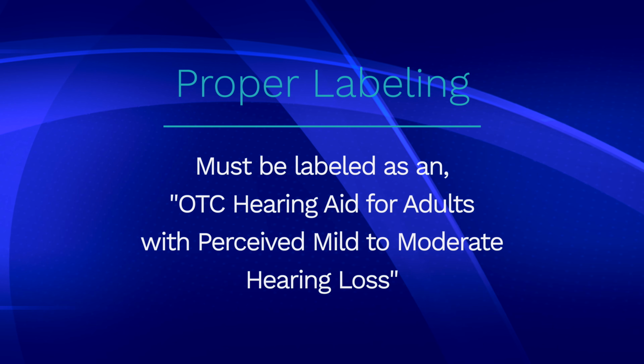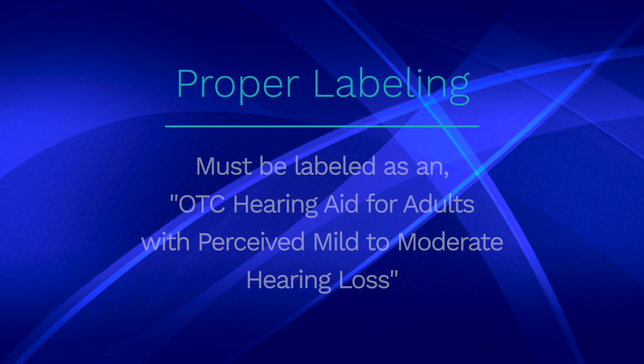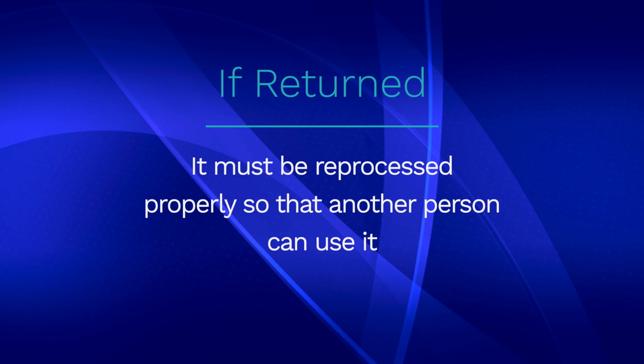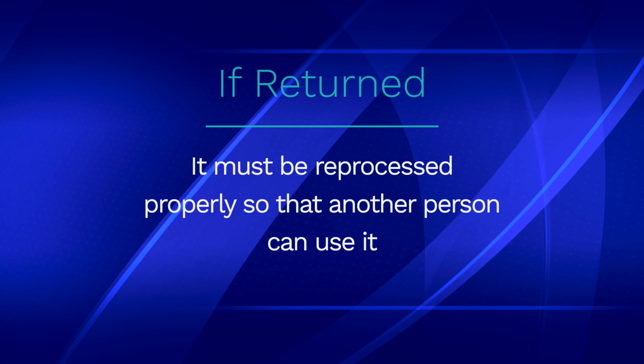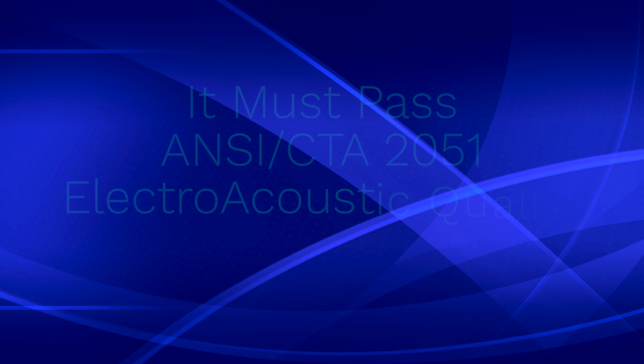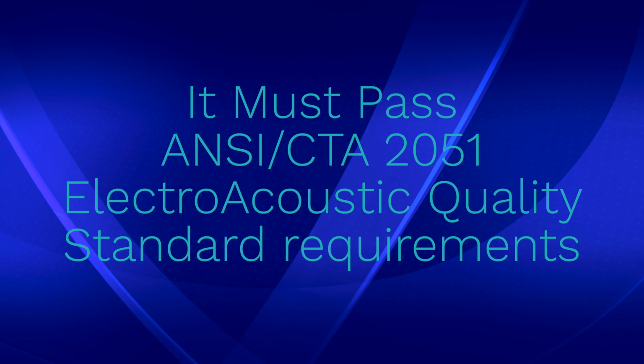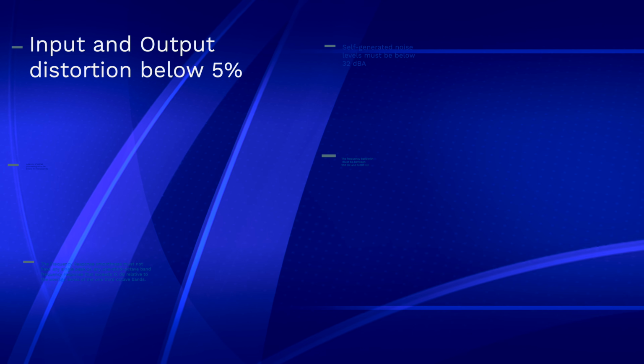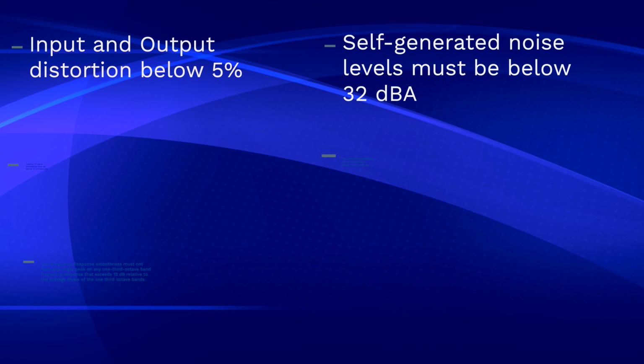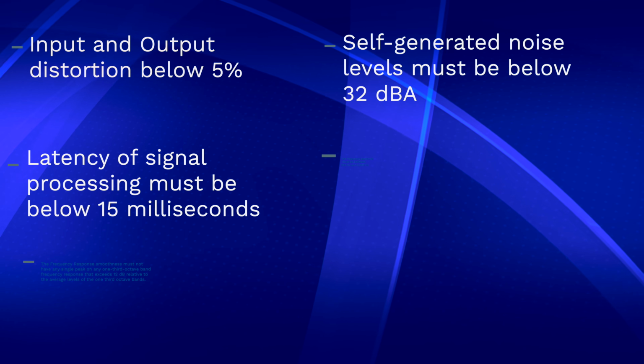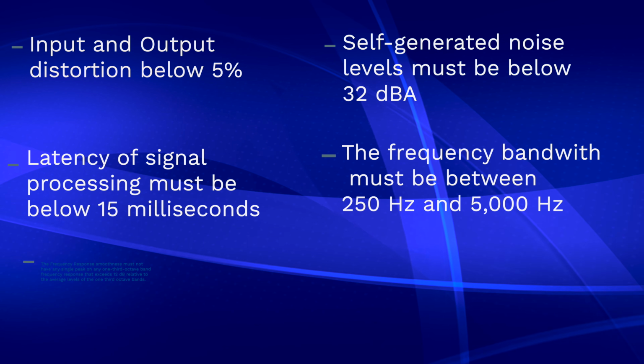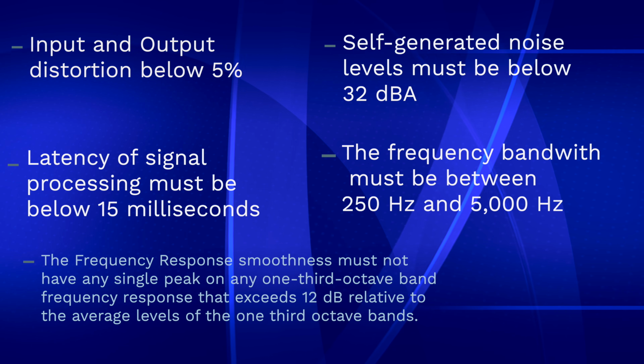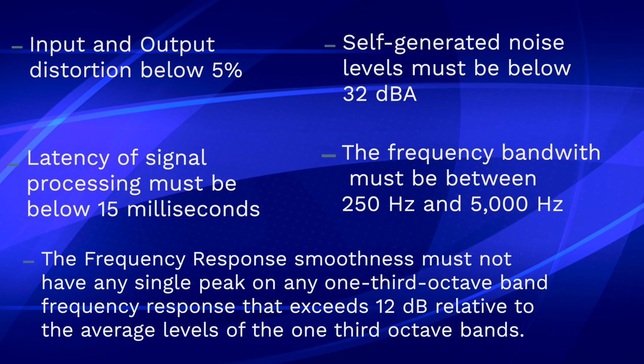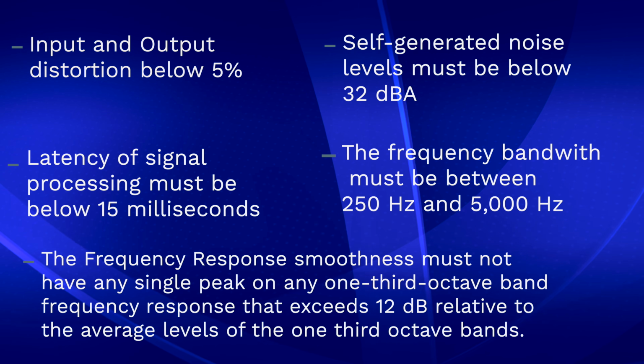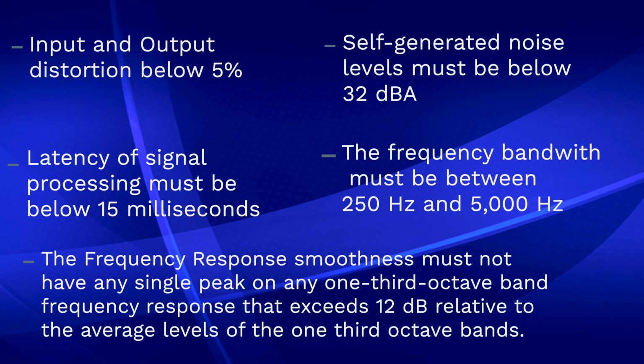It must be labeled as an OTC hearing aid for adults with perceived mild to moderate hearing loss. If an OTC device is returned for a refund, it must be reprocessed properly so that another individual can use it, which admittedly is still pretty vague. It must pass ANSI CTA 2051 ElectroAcoustic quality standard requirements. Now bear with me here, this includes input and output distortion below 5%, self-generated noise levels must be below 32 dBA, latency of signal processing must be below 15 milliseconds, the frequency bandwidth must be between 250 Hz and 5000 Hz. And the frequency response smoothness must not have any single peak on any 1/3 octave band frequency response that exceeds 12 decibels relative to the average levels of 1/3 octave bands.